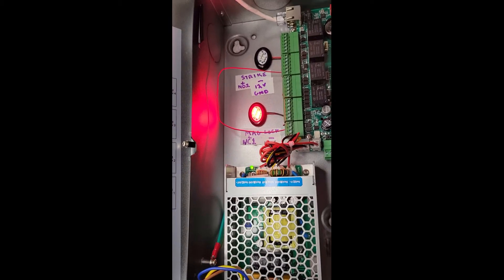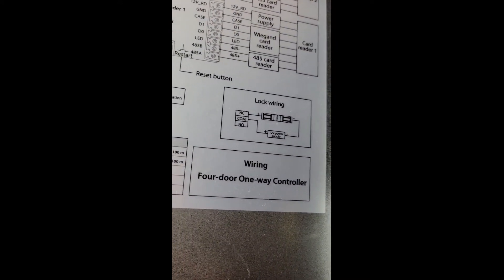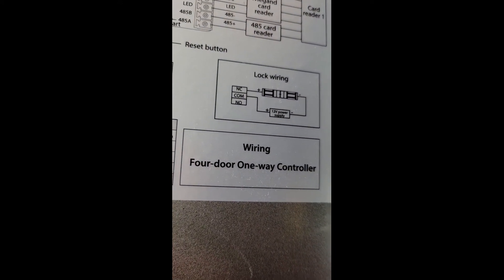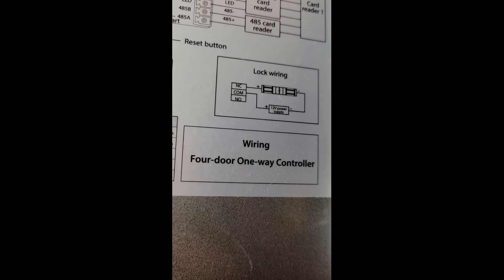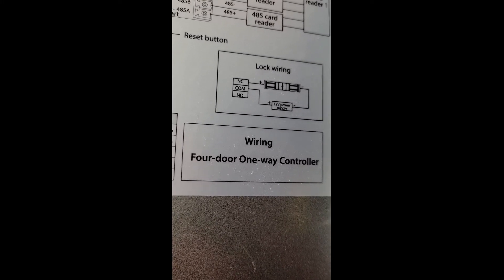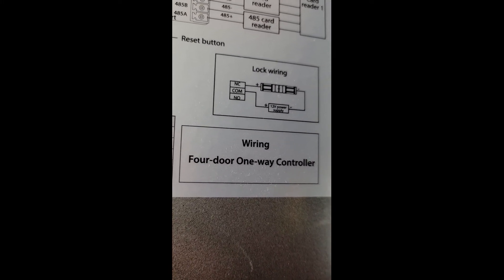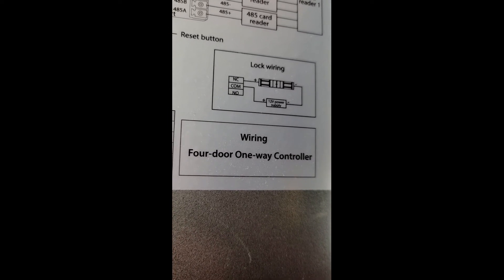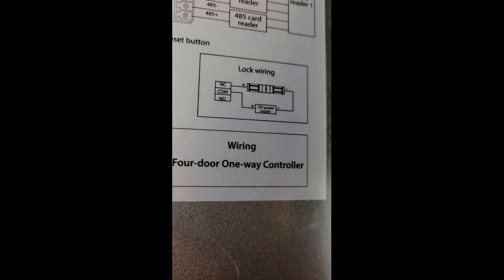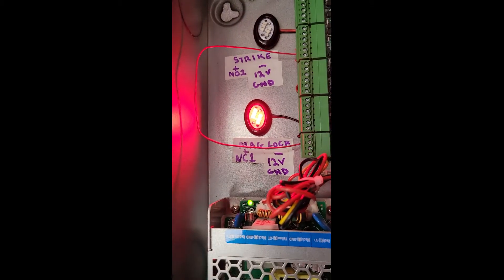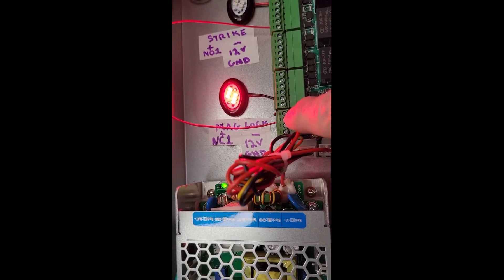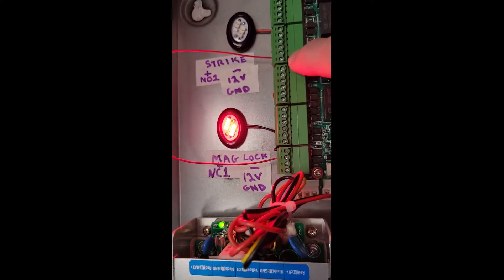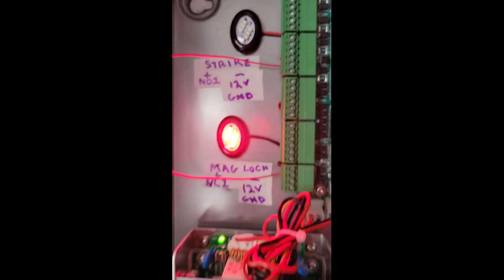On the lock side, we will utilize the 12 volt power supply that's on board, and use this lock wiring method. So the positive side from our power supply will jump over to the common one. Since we're using door lock one, we're going to land the plus from the 12 volt power supply to the common one. We can see that this wire here is our jumper from our power supply positive to our common one connection on this terminal.